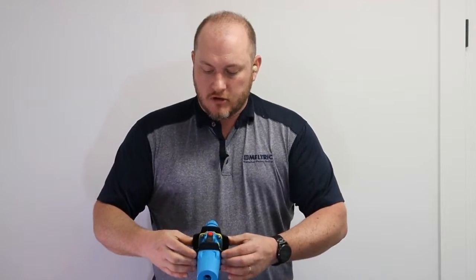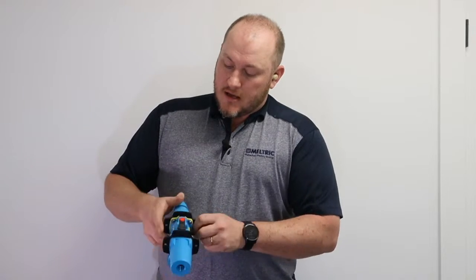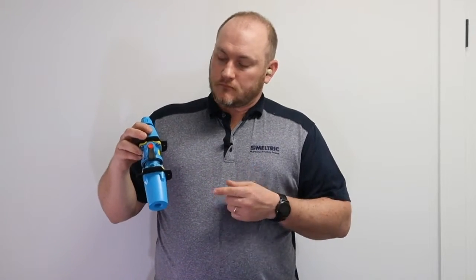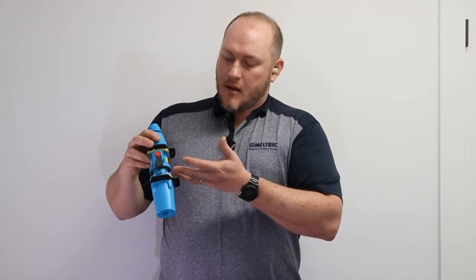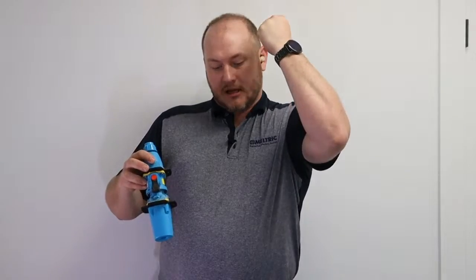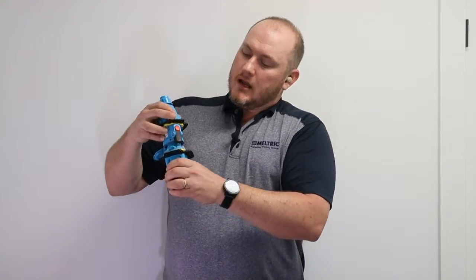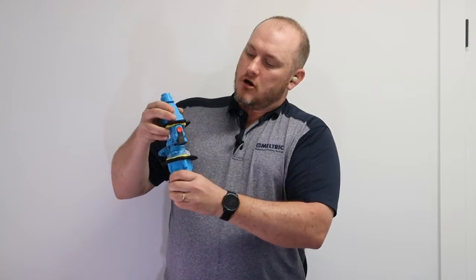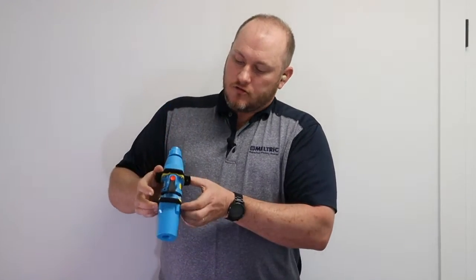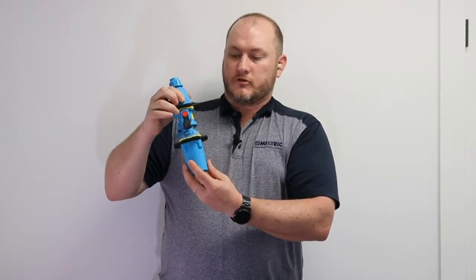We then close on those contacts. So it's kind of interesting though, because if we were to close on a fault and create an arcing event that happens in there, this plug has the potential to kind of blow out from the receptacle, because we're going to create an explosive event that happens inside of there. That opening and closing of the dead front shutter is also engaging these little ears on our inlet. So when it's in there, if we are to close on the fault, it will just pop open and still stay closed. Any arcing that's happening in there is staying contained within the plug. The plug is not ejecting from the device.